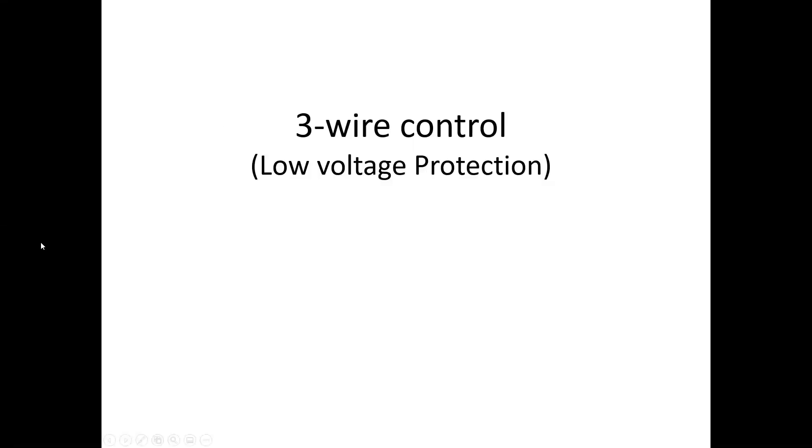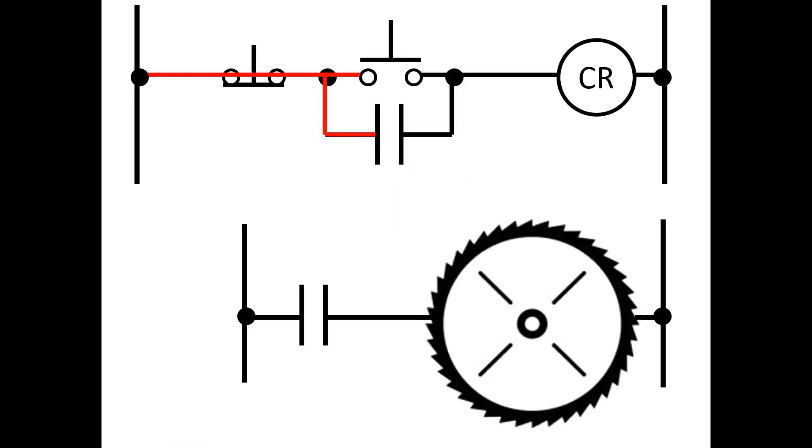Three-wire control, low voltage protection. This type of control utilizes two separate field devices, a normally closed and a normally open, typically but not always, for the starting and stopping portion of the circuit. And they're momentary contact devices, as in they're spring loaded and they return to their original position once they have been released by a user.